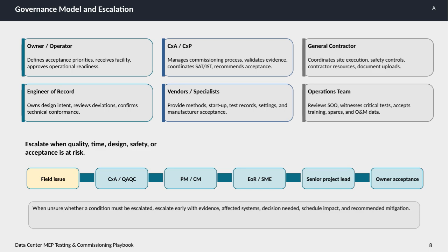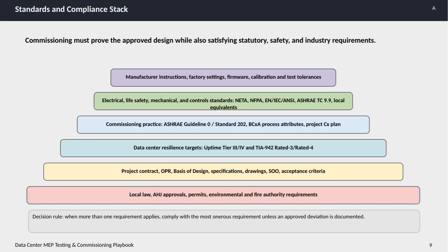and operational data center. Here we have the standards and compliance stack for data center MEP testing and commissioning. The key point is that commissioning must verify the approved design, while also meeting all statutory, safety, and industry requirements. This starts with complying with local laws, obtaining approvals from authorities having jurisdiction, securing necessary permits, and adhering to environmental and fire safety regulations. Next, the project contract, owner's project requirements, basis of design documents, specifications, drawings, sequence of operations, and acceptance criteria all set the framework for what the commissioning must achieve.